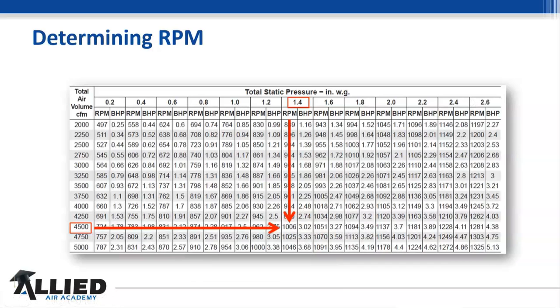So we look at this, and we got a 1.4 inch static pressure, and we know our RPMs is 1006. So if we go over and look at this chart, this unit is putting out 4,500 CFMs. That's going to help you out a lot.